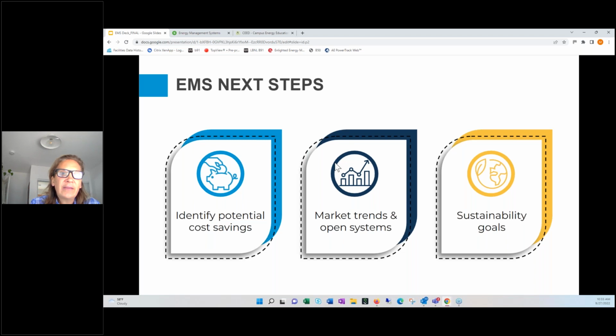Where what an analytics software does is it has all the smarts already and a lot of the logic built in. So it will read all those data points that I just pointed out, and it'll do the analysis and logic for you. And what it'll spit out instead is, say, yesterday there were 3 hours out of the day where you should have been in economizer mode and you should have been saving energy, and this is how much you would have saved had you been in economizer mode. And that's what an analytic software does, is that it takes some of those typical energy efficiency measures, and it does that analysis for you behind the scenes and then spits out useful information.